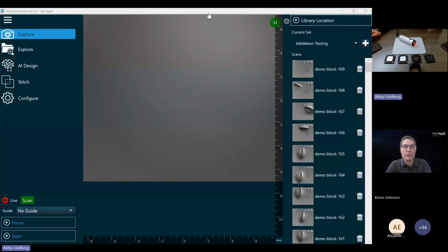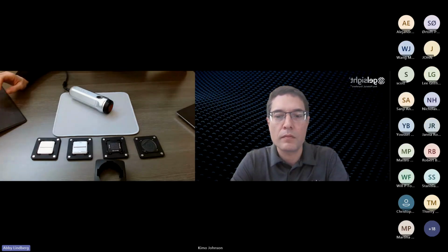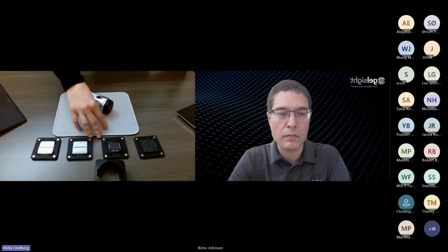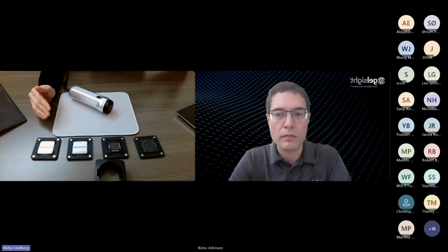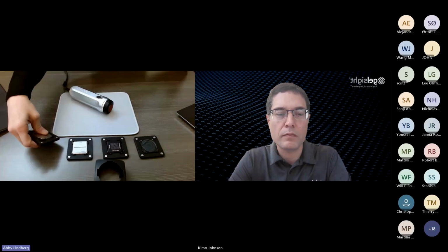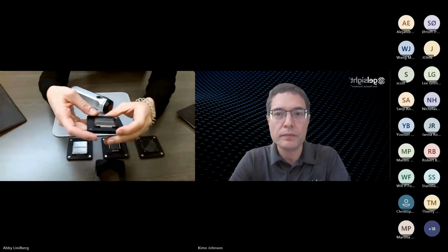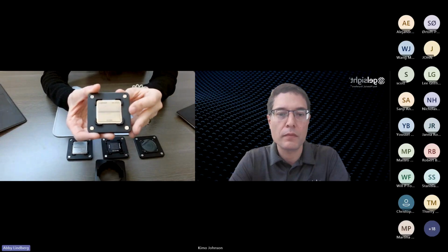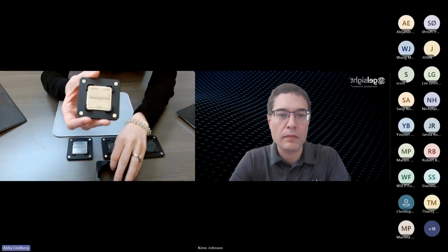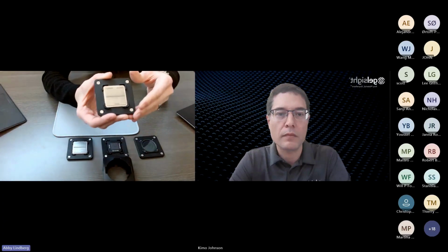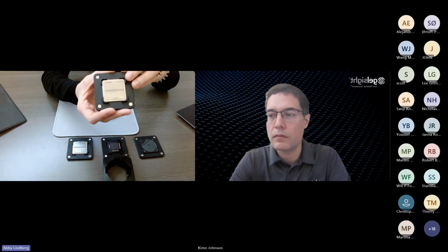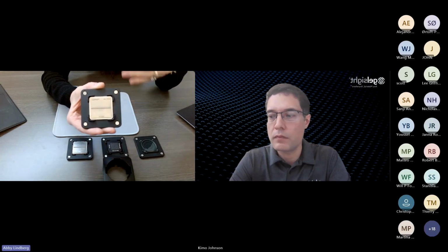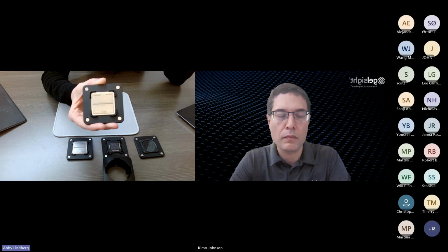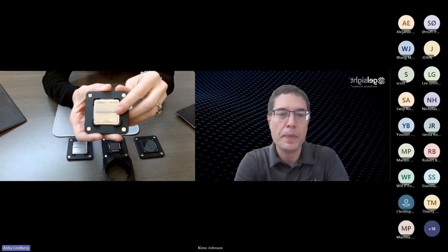I want to hold up the validation plate with a larger video display. The calibration process has to happen for every gel before we can use it. But rather than each time we use the system, since it's not a requirement, we would want to validate. So here we have our validation target. Another plate uses the same alignment fixture as our calibration plates. This is what we can use to do a quick pass/fail check if we're still reporting within tolerances. So Kimo, do you think you could talk a little bit about the target design and what we have on this target?